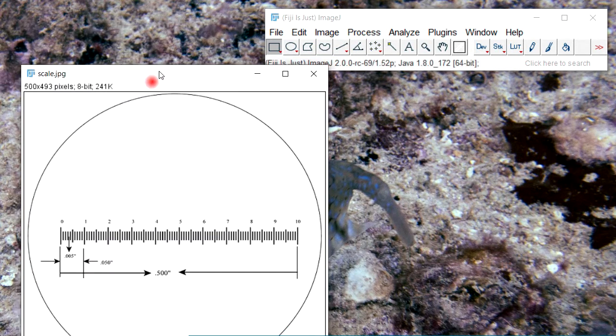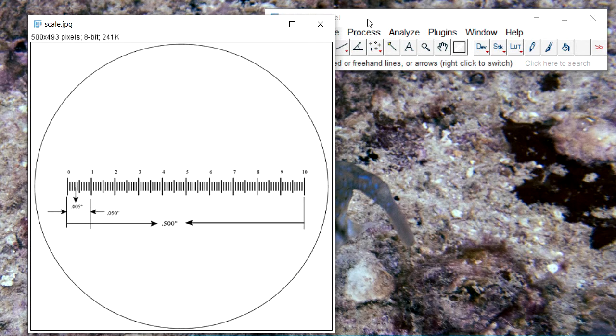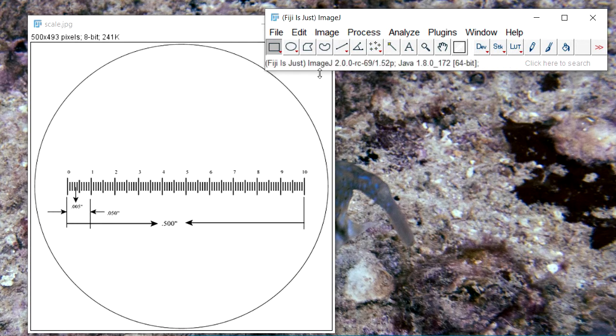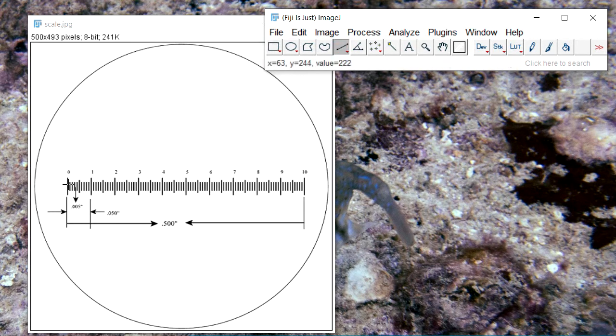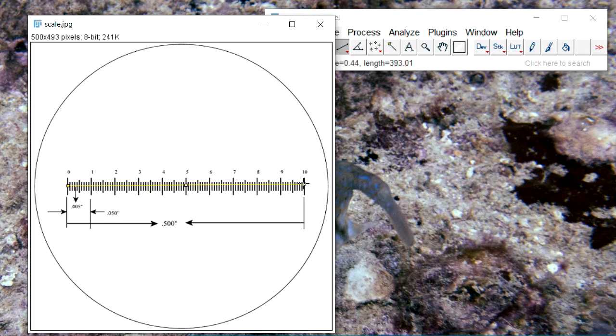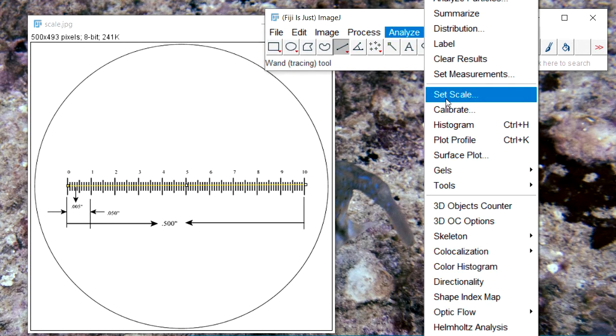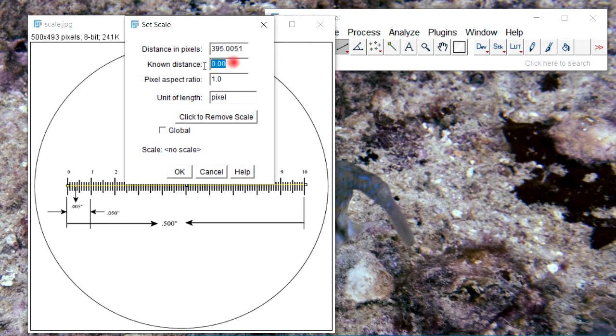Normally for you, this will be done by using an image of a scale on your microscope. Then you go to the line tool and left-click and drag to select the scale. Then you go to Analyze > Set Scale, and here we will say that this will be one millimeter — so known distance is one and unit is millimeters. Then click Global so that the scale applies to all images that we want to measure, then click OK.